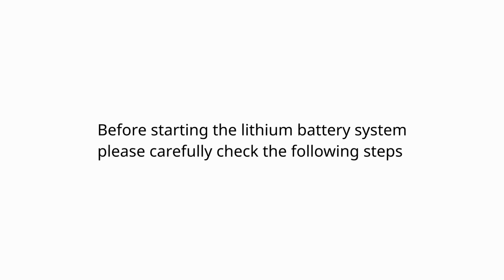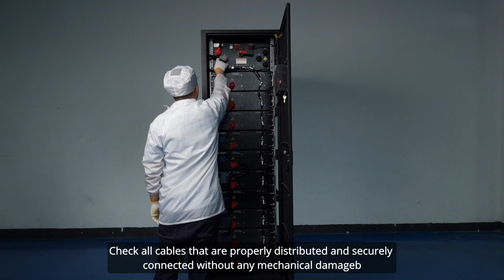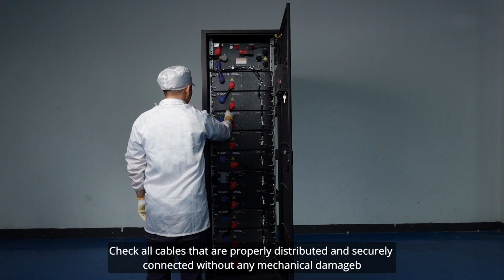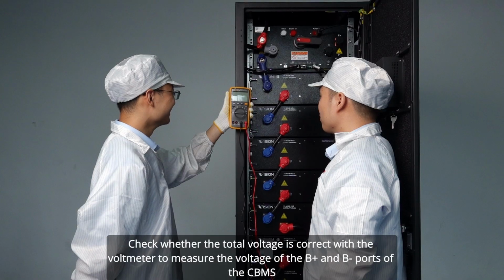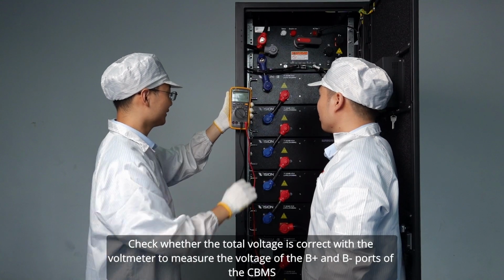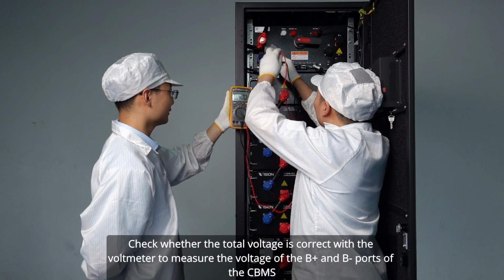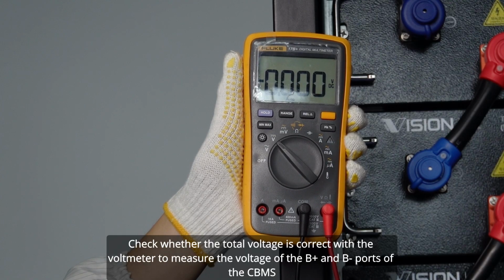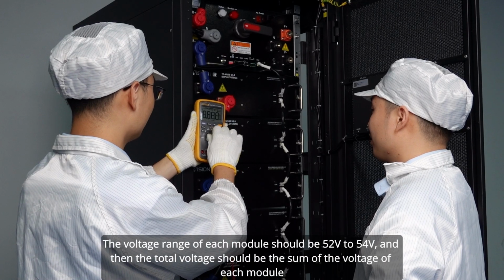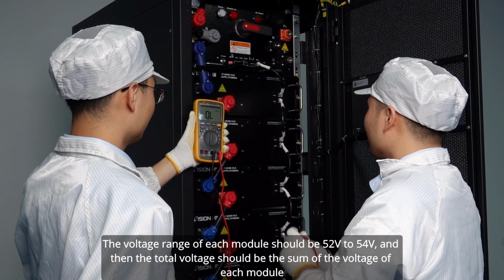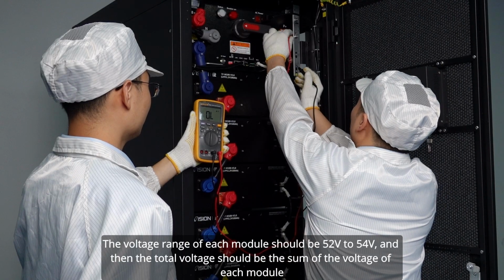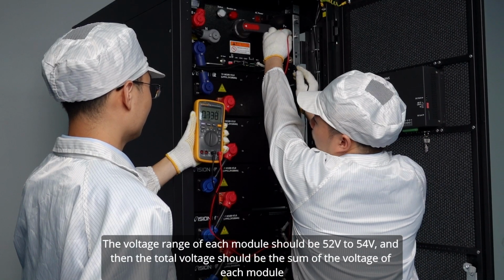Step 6. Installation Inspection. Before starting the lithium battery system, please carefully check the following steps. Check all cables that are properly distributed and securely connected without any mechanical damage. Check whether the total voltage is correct with the voltmeter to measure the voltage of the B+ and B- ports of the CBMS. The voltage range of each module should be 52V to 54V, and then the total voltage should be the sum of the voltage of each module.